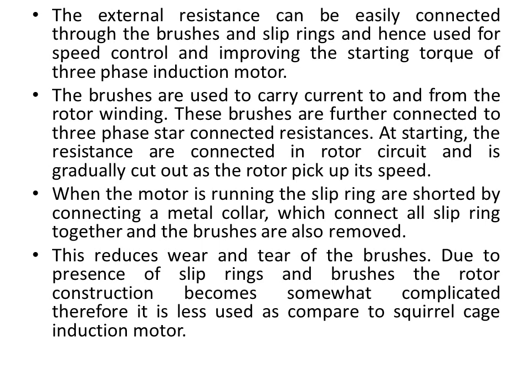Because of the slip ring and brushes, we can easily connect an external resistance so that we can control the speed and improve the starting torque of the three-phase induction motor. Here, brushes are used to carry current to and from the rotor winding. Three brushes are further connected to three-phase star connected resistances.